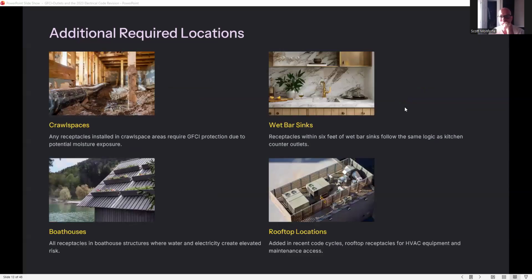Additional required locations: crawl spaces, wet bar sinks, boathouses, rooftop locations. So any receptacle installed in the crawl space area requires GFCI protection due to potential moisture exposure. Wet bar sinks, receptacles within 6 feet of a wet bar sink, following the same logic as a kitchen. Boathouses, all receptacles in boathouse structures where water and electricity create elevated risk. Rooftop locations, added in recent code cycles, rooftop receptacles for HVAC equipment and maintenance access.